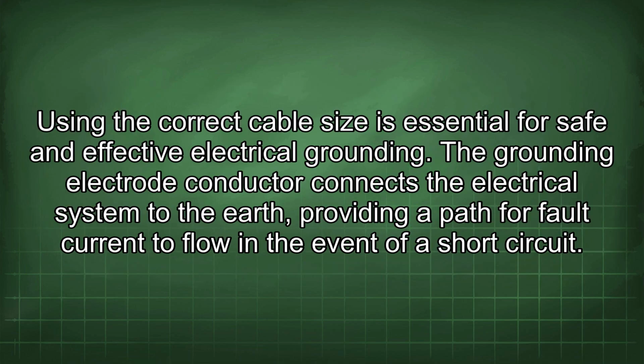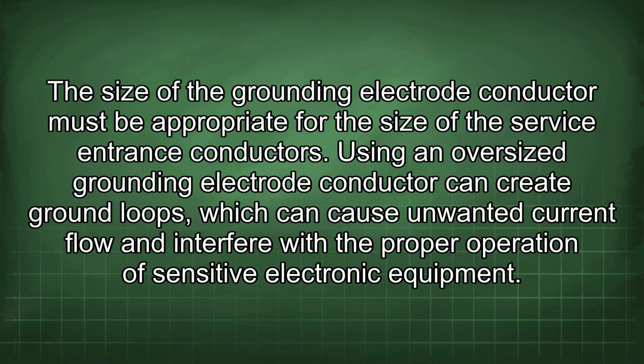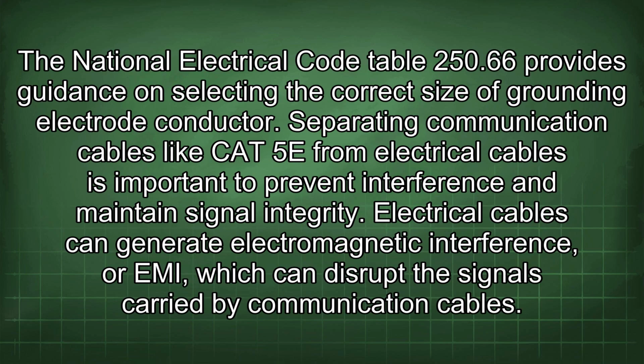Using the correct cable size is essential for safe and effective electrical grounding. The grounding electrode conductor connects the electrical system to the earth, providing a path for fault current to flow in the event of a short circuit. The size of the grounding electrode conductor must be appropriate for the size of the service entrance conductors. Using an oversized grounding electrode conductor can create ground loops, which can cause unwanted current flow and interfere with the proper operation of sensitive electronic equipment. The National Electrical Code Table 250.66 provides guidance on selecting the correct size of grounding electrode conductor.